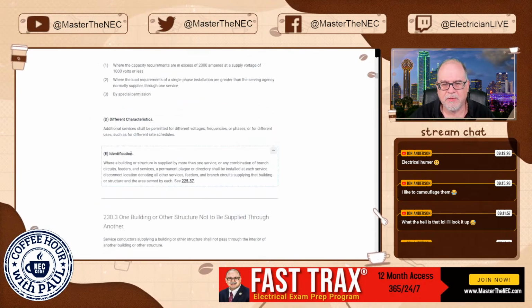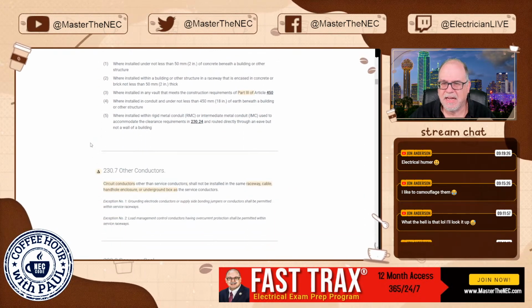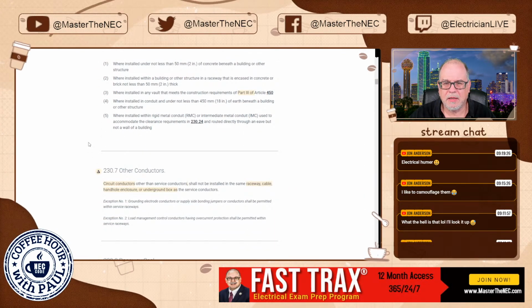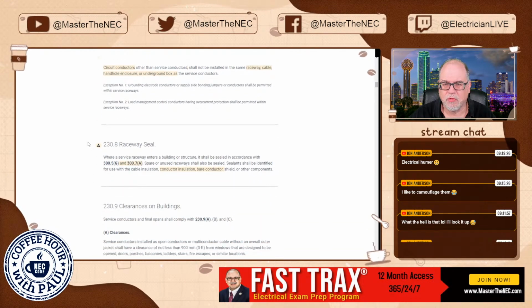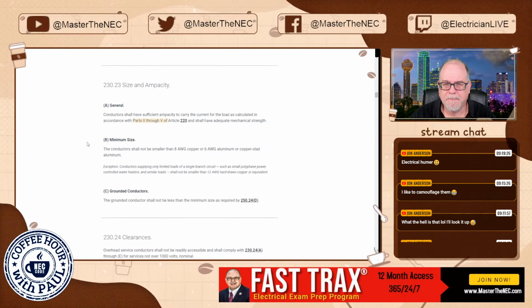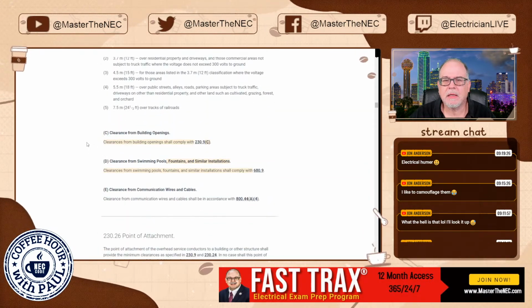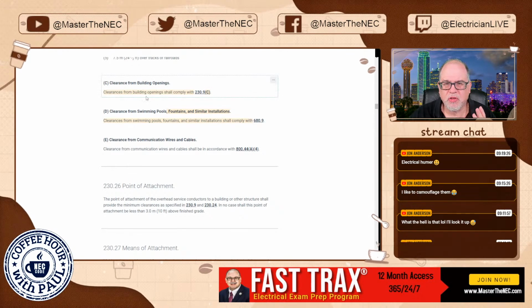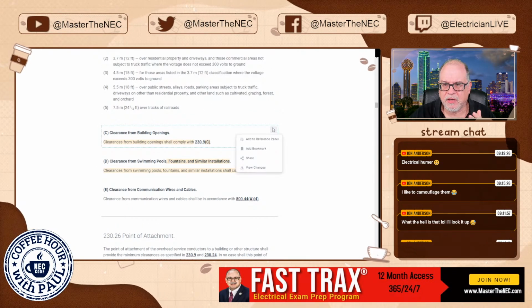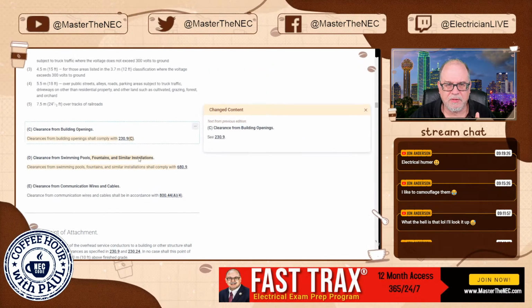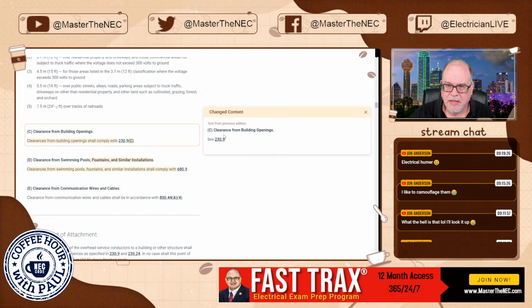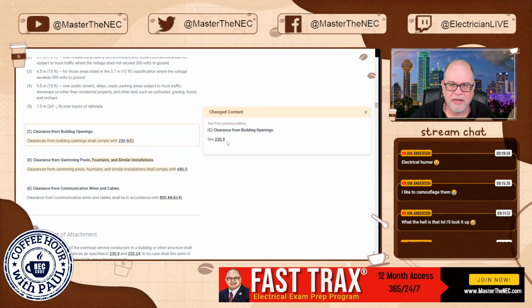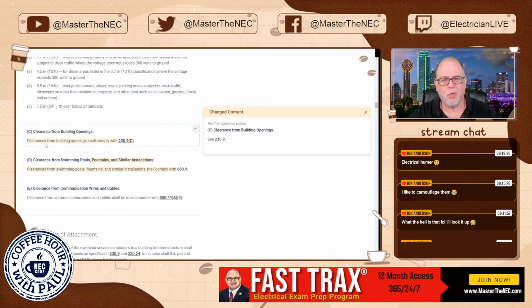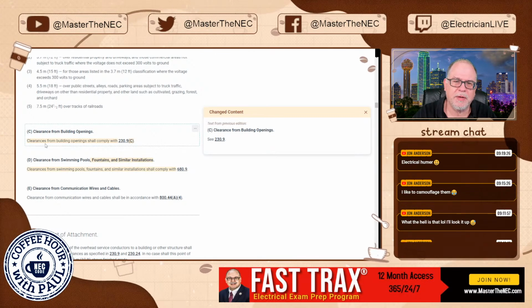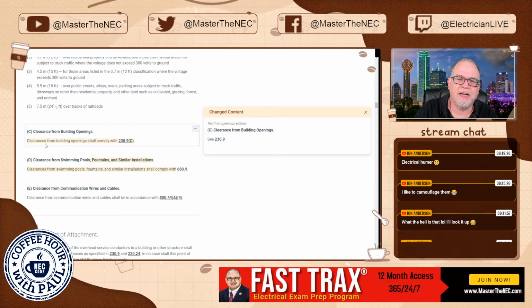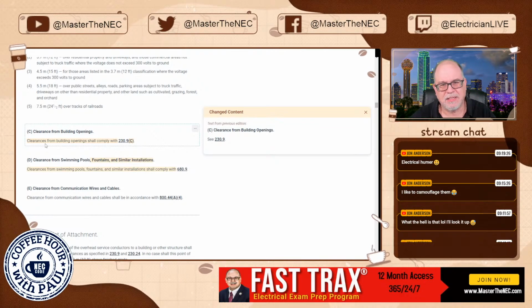All right, let's see if I can go down and find some of these. Some are just changes, nothing overly significant that we'll spend any significant time on. Some of these are just verbiage changes, just to give you an example. When we look at it here, I'll click this, and you can see for C, for example, it just said clearance of building opening see 230.9, and here it's giving you a little more direction. The clearances from building openings shall comply with 230.9(C). So it kind of sends you there.